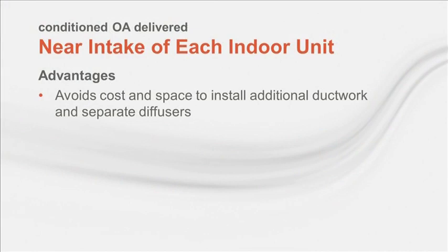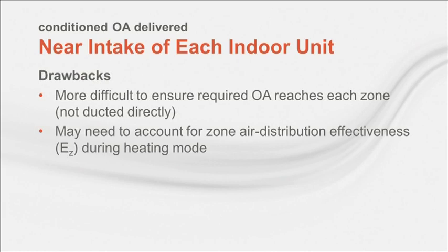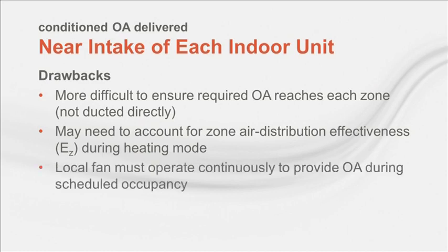Probably the main advantage of delivering outdoor air to the plenum is that it avoids some of the cost and space needed to install the additional ductwork or diffusers that would be required if the outdoor air were ducted directly to each zone or unit. However, it's difficult to ensure that the required amount of outdoor air reaches each zone since it's not ducted directly. In addition, since the fan inside the VRF terminal is used to deliver outdoor air to the zone, that fan must operate whenever the dedicated outdoor air system is operating.